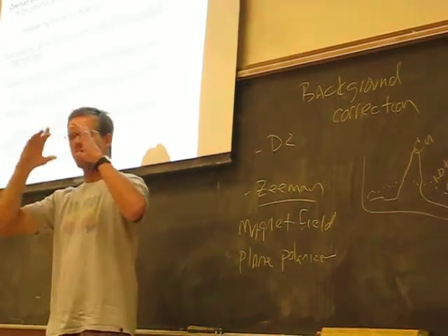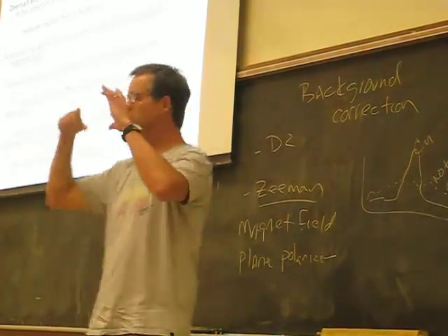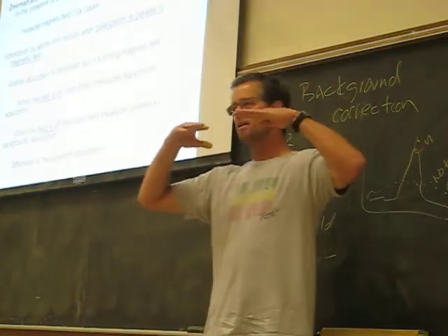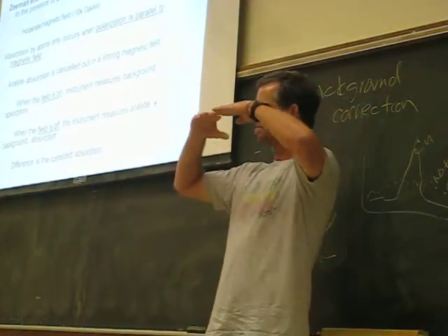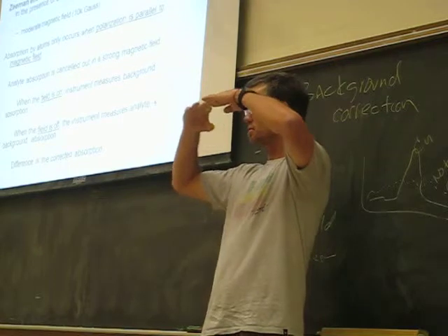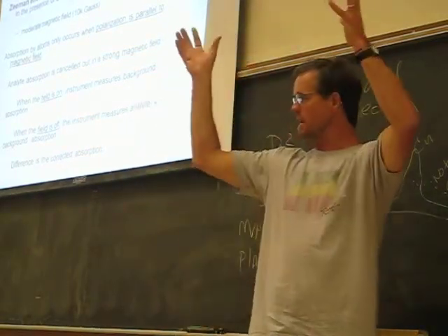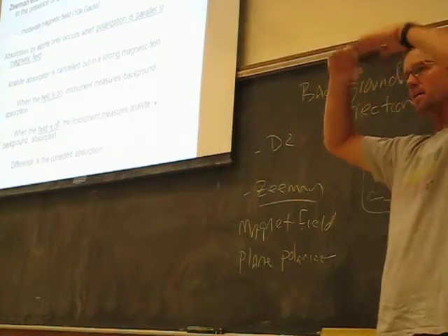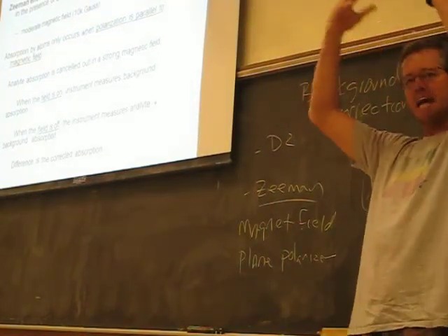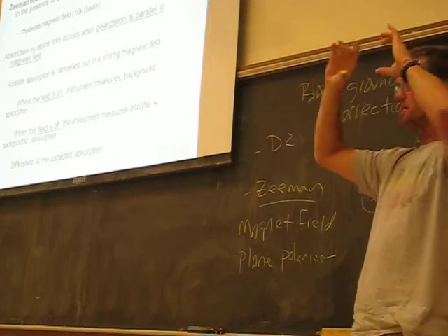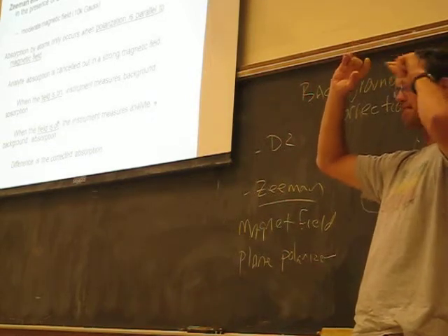During the cycle where you're actually reading absorbance, you've evaporated the sample during the initial evaporation stage, then you heat up a little more and char your sample, driving off all the organics and interfering things. Then you heat it up really hot and vaporize and atomize your sample into free atoms, up in the gaseous phase in that little graphite tube.